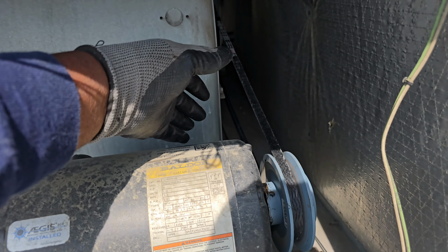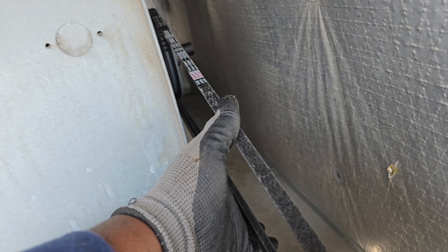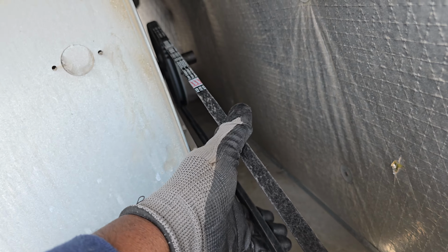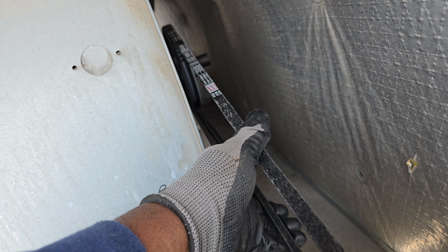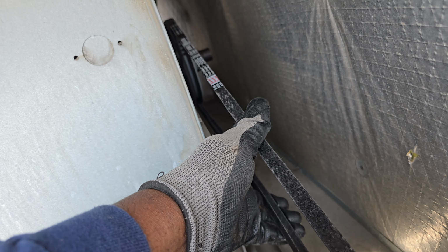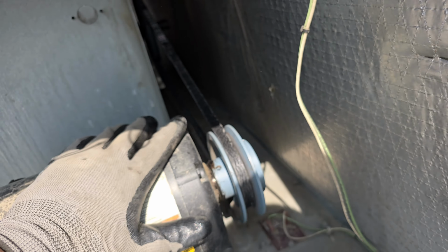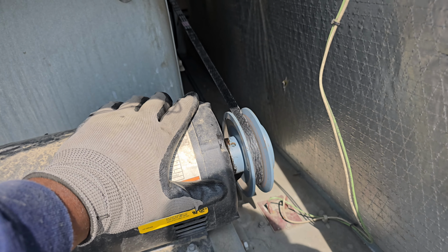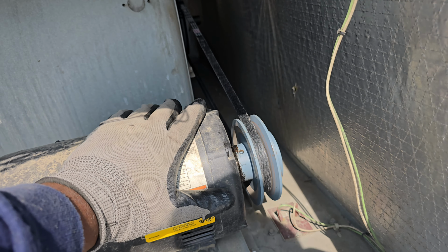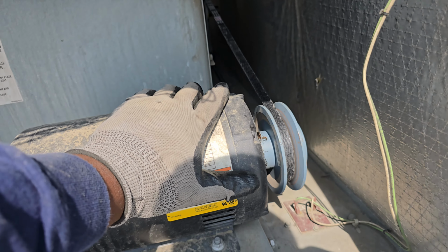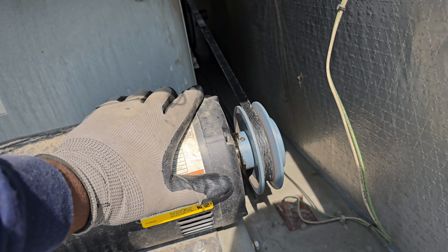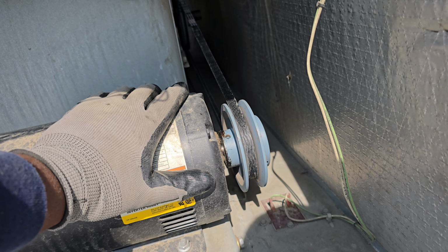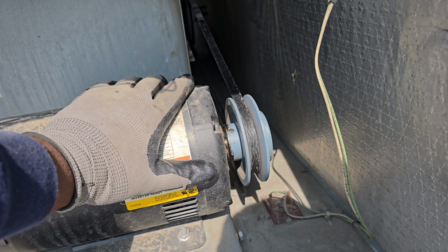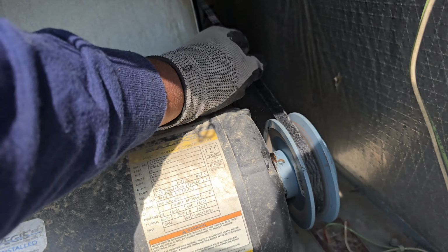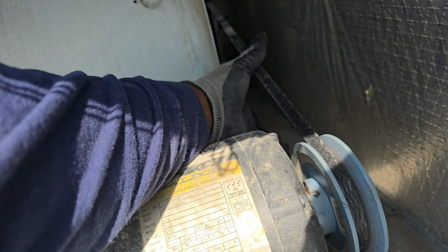Now that my belt is in, take a look at the tension. If the tension is too tight, it will make the motor slow and put more force on it, causing the motor to draw more amps to give you airflow, which isn't good for the motor. So make sure you don't put in too much tension, but also don't let it be too loose.